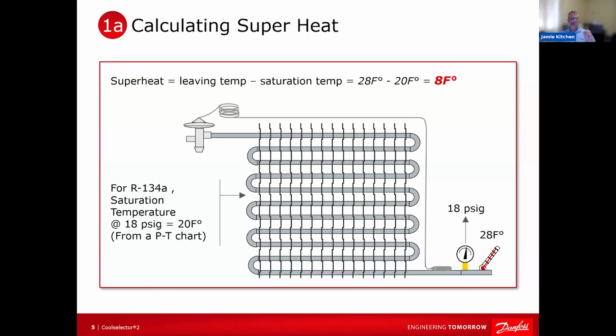So if you measure the pressure in the system and convert that to saturation temperature, you'll end up with a value. In this case, 8 or 20 degrees Fahrenheit. That means the refrigerant is changing state. So since we're adding heat, it is boiling off. Now remember, it doesn't matter the temperature or pressure. If the refrigerant is warmer than the air, it's going to condense. Doesn't matter what the pressure or temperature is. If it's warmer than the surroundings around it, it's going to give up heat and condense. If it's cooler, it's going to absorb heat, right? One of the first things you learn in thermodynamics. So in this case, it is cooler than the air. We're absorbing heat, so we're changing state.